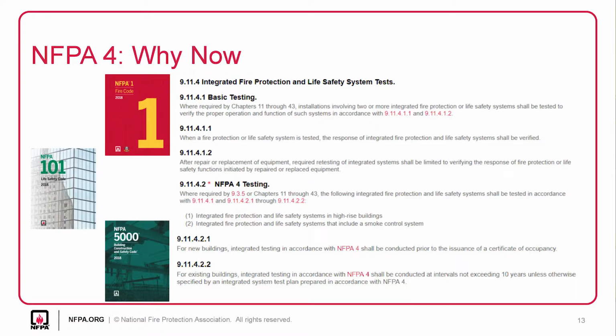Basically, here's the text on the screen. This is the text from NFPA 101, which is the same as the text in 5000, and then the 101 text is extracted into the NFPA fire code. What this says is you have basic testing that you need to do. The basic testing, as it says, is anytime you test a fire alarm system, you need to then make sure that for any of the integrated systems with it, the intended functions are performed. It doesn't tell you how to do it. It just says you have to look at it and make sure that you're getting the correct responses.